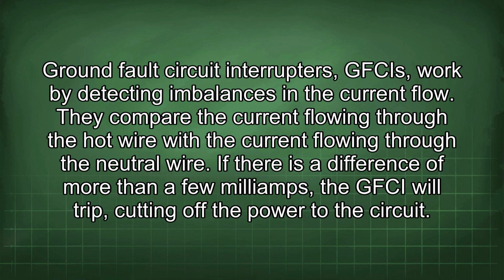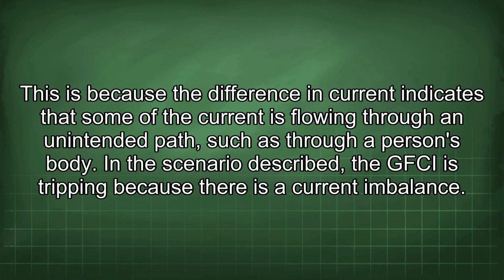Ground fault circuit interrupters, GFCIs, work by detecting imbalances in the current flow. They compare the current flowing through the hot wire with the current flowing through the neutral wire. If there is a difference of more than a few milliamps, the GFCI will trip, cutting off the power to the circuit. This is because the difference in current indicates that some of the current is flowing through an unintended path, such as through a person's body.